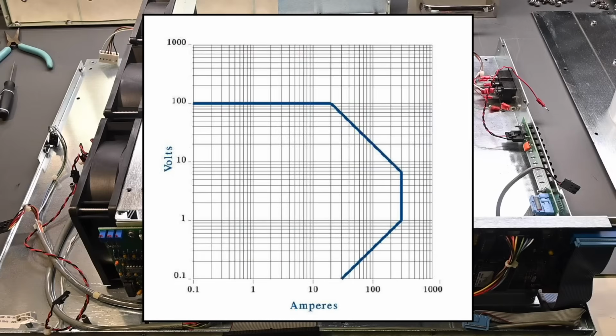So what those numbers mean is that the maximum input voltage is 100 volts DC, the maximum current this can draw is 300 amps, the maximum power dissipation is 2000 watts or 2 kilowatts. But you can't do the maximum voltage and current at the same time because of course that would far exceed 2000 watts. And this has protection circuitry inside of it that prevents over current and over power and other situations that would damage the instrument.